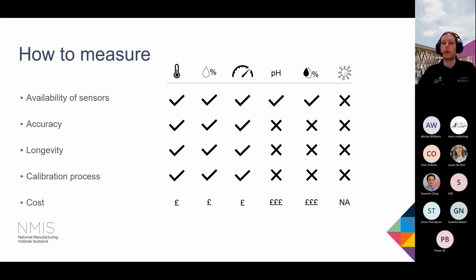And again, here's where accuracy is relative. I don't need to know if it's moved by 0.1 of a millimeter—it's got about 15 centimeters of travel. So within a few millimeters is plenty of accuracy to get an indication of whether your tank is running low or sitting high. Next, we come on to pH.